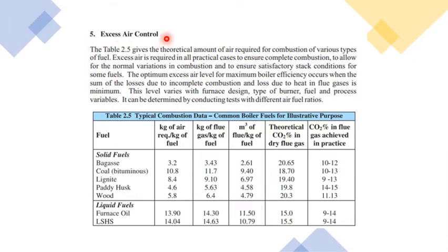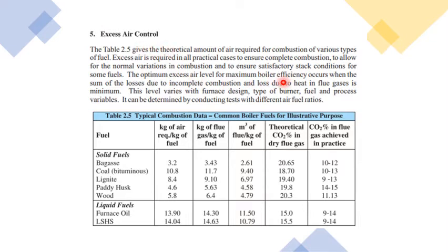The fifth point is excess air control. You need some excess air, but too much excess air lowers boiler efficiency. The optimum excess air level for maximum boiler efficiency occurs when the combined losses due to incomplete combustion and heat in flue gases are minimized. You must control the excess air supply — enough but not too much — to maintain optimal combustion and efficiency.